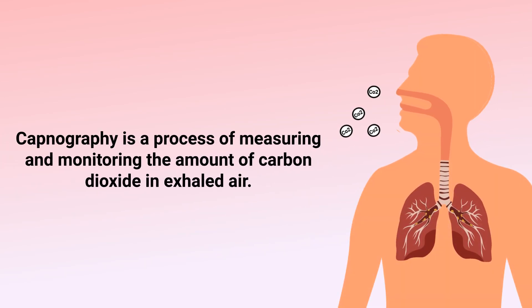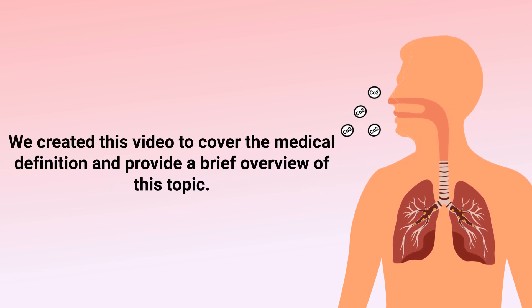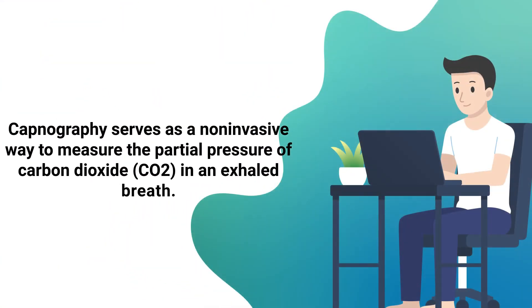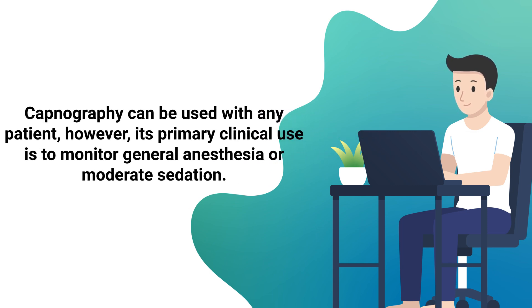Capnography is the process of measuring and monitoring the amount of carbon dioxide in exhaled air. As previously mentioned, capnography serves as a non-invasive way to measure the partial pressure of carbon dioxide in an exhaled breath. In respiratory care, capnography can be used with any patient; however, its primary clinical use is to monitor general anesthesia or moderate sedation.